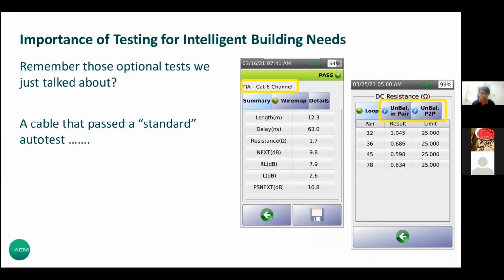I hope everyone is still good. Again, reviewing what I said earlier: this DCR is not just measuring the DC resistance of the whole cable. First we also measure the unbalance within the pair, and then the unbalance pair to pair. This helps you qualify your cable based on the DCR, whether it's good enough to perform PoE.